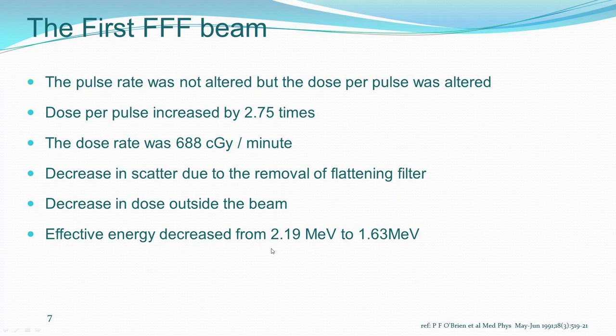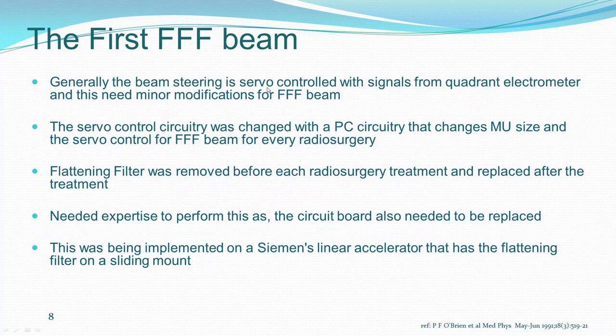There was decreased scatter and decreased dose outside the beam due to removal of the flattening filter. The effective energy decreased from 2.19 MeV to 1.63 MeV for a 6 MV photon beam, due to lack of beam hardening. Beam steering is servo-controlled with signals from the quadrant electrometer, and this needed minor modifications for the Triple F beam — two electronic changes: the servo control circuitry and the PC circuitry for dose per MU. This needed expertise and was somewhat time-consuming.